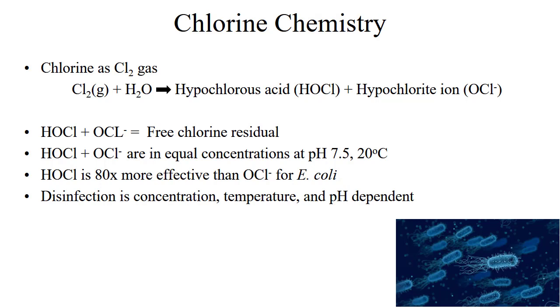As the pH goes below 7.5, hypochlorous acid becomes the dominant compound. Hypochlorous acid is the workhorse of the two compounds and is 80 times more effective than the hypochlorite ion for disinfecting E. coli, a common bacteria. Disinfection is influenced by the concentration of the disinfectant, the temperature of the water, and the pH of the water.